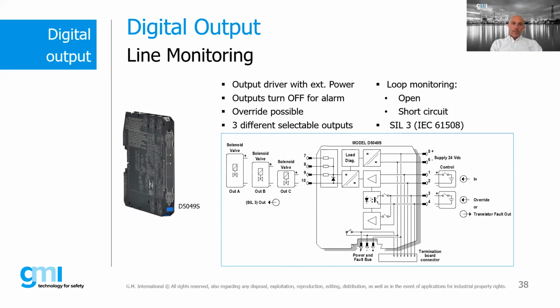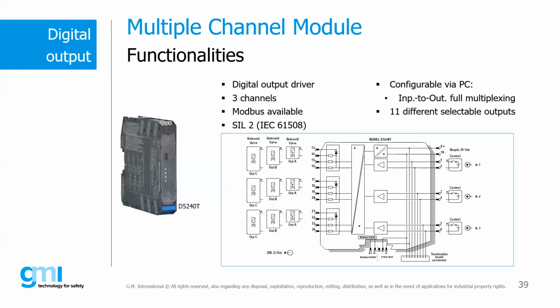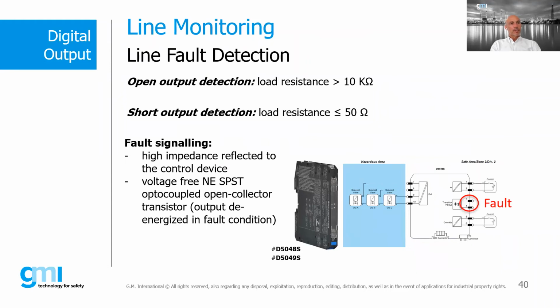In this case, there are 3 different selectable outputs, also to match different loads, and with the loop monitoring, such as open and short circuit, suitable for SIL 3 applications. We also have a different multiple channel solution, where you see that the size of the modules is increased, with functionality like Modbus output and complete full multiplexing. In this case, there are 11 different selectable outputs. It is a very useful and flexible device for a lot of applications. Massimo, maybe you can explain a little bit better what we mean by line monitoring for digital outputs.